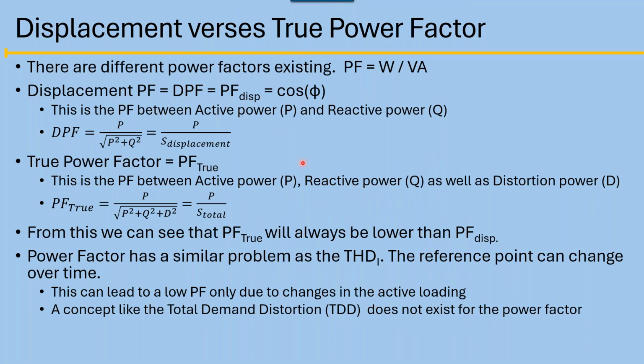And here are our formulas for this. I had to give you a little math just to make this worth your while. So the displacement power factor that I was talking about is P over the square root of P squared plus Q squared, where P squared plus Q squared gives the kVA. The true power factor includes P, Q, and D, and that's your total. Because I've got this D component in here, I can always say that the true power factor is going to be lower than the displacement power factor.